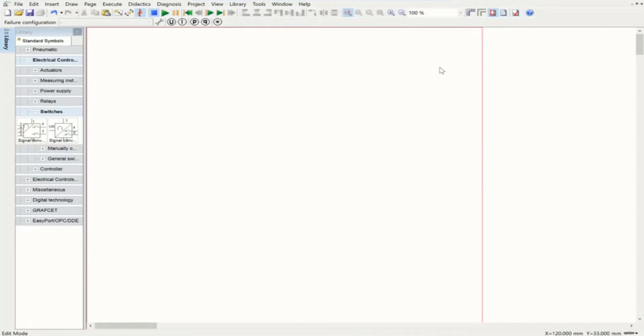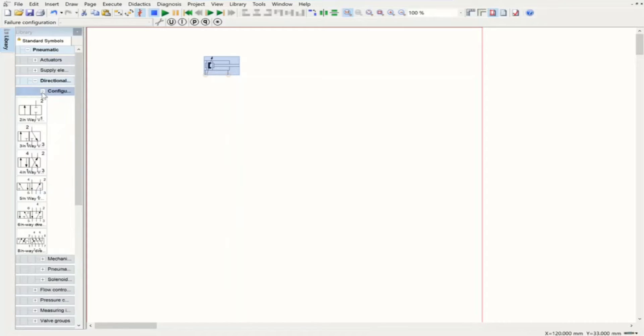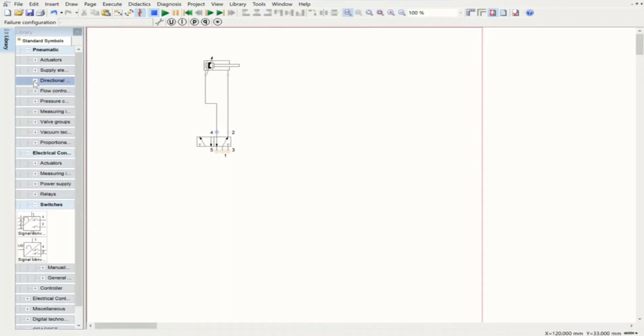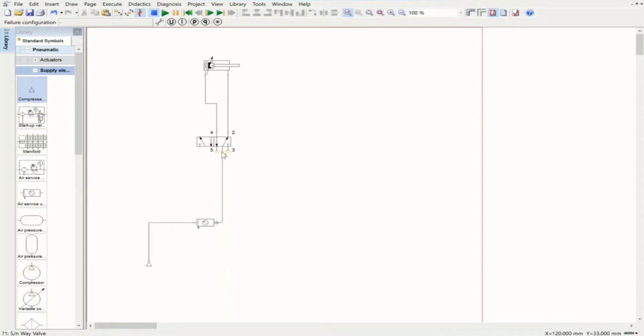We saw the circuit of an oscillatory motion related to electropneumatic systems. Now I'm going to design that specific circuit. For the pneumatic side, we need an actuator — a double acting cylinder. For that double acting cylinder, we have a directional control valve with five ports and two positions. Then we add the air service unit as the supply element, along with one compressed air supply. Both are connected accordingly, and the two exhaust ports are configured.